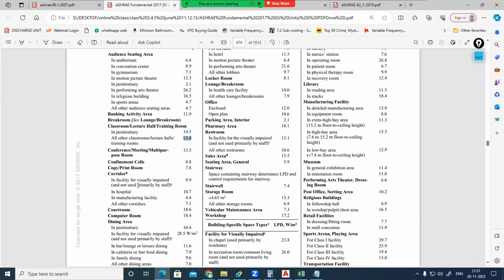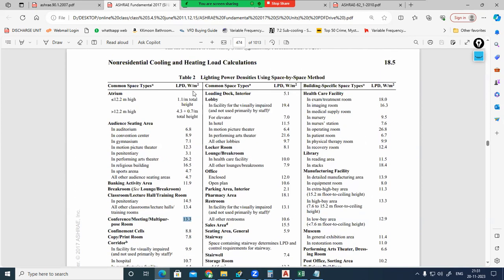13.4. But for a conference room, if you want to consider multi-purpose or meeting use, take 13.3, which means for 1 meter square you consider 13.3. Like that, how many meter square of floor area? 77.8 meter square. So 77.8 into 13.3, you can find that. Okay, this is from the non-residential cooling and heating chapter only.